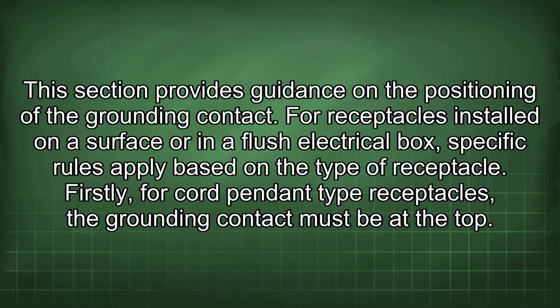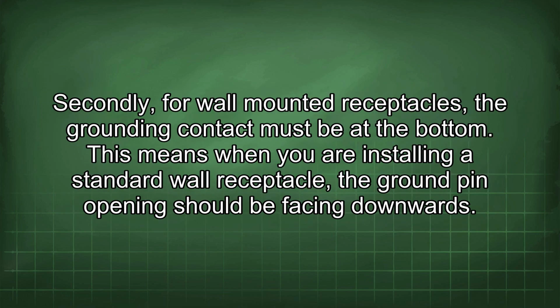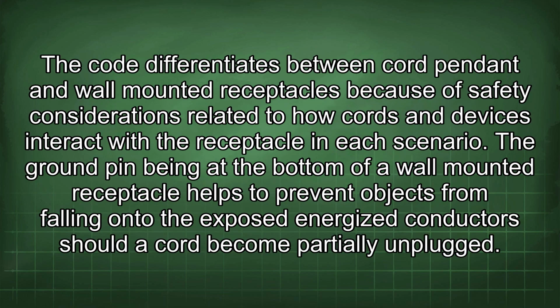For receptacles installed on a surface or in a flush electrical box, specific rules apply based on the type of receptacle. Firstly, for cord pendant type receptacles, the grounding contact must be at the top. Secondly, for wall-mounted receptacles, the grounding contact must be at the bottom. This means when you are installing a standard wall receptacle, the ground pin opening should be facing downwards. The code differentiates between cord pendant and wall-mounted receptacles because of safety considerations related to how cords and devices interact with the receptacle in each scenario.